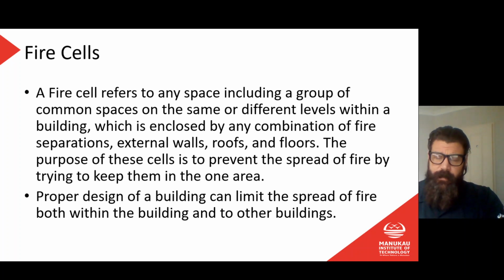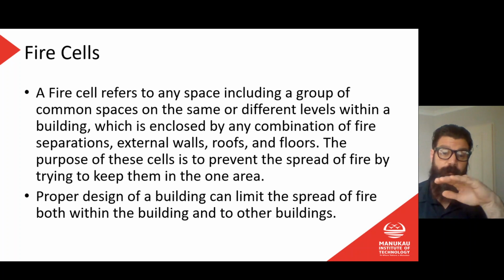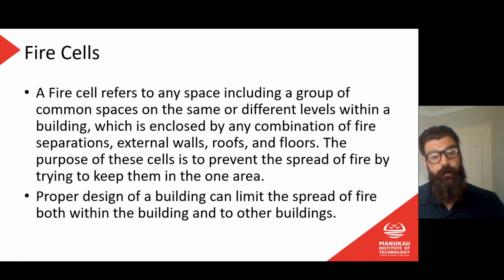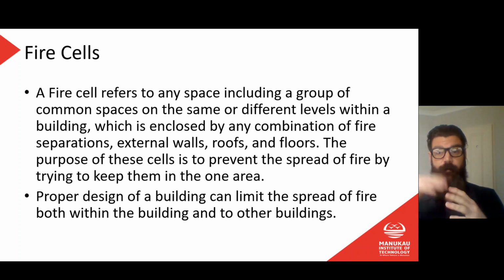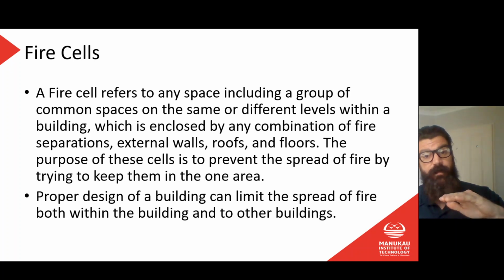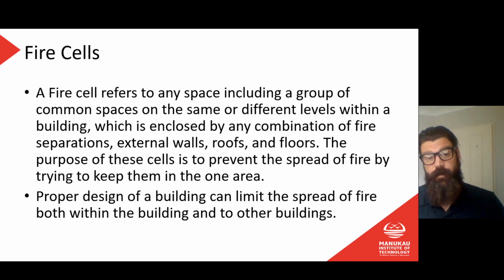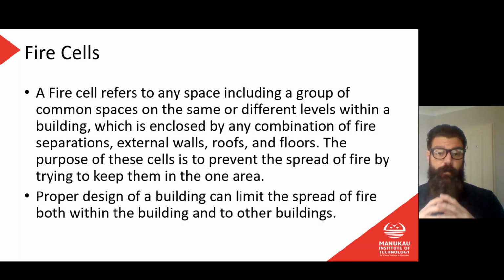So the most common place that you'll come across a fire separation is in floors, the floors between separate levels on a building. So the idea there, of course, is that if we have a fire on the bottom floor, say the second floor, then the people on the above floors are going to be able to get out before that fire threatens the floors above. So if you think about P block at MIT, the floors would be fire separations. Generally they'd be fire separations by design. They'd be made out of concrete, so concrete by itself is an effective fire separation.